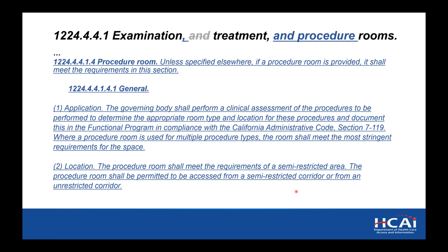for procedure rooms. They also addressed, which I think we should have in more places, the encroachments into the minimum floor area. This could be like a column or something that might encroach into the clear floor area required for a procedure room. It does not extend more than 12 inches into the minimum floor area. Where a sterile field is provided, the encroachment shall not extend into the sterile field, which is typically 5 feet around the bed or the table. Encroachment width along each wall does not exceed 10% of the length of that wall. So this is really good for when we're working with an existing space, like a remodel, and trying to convert that to a procedure room. You'll have a little bit of guidance on what that clear space would allow.